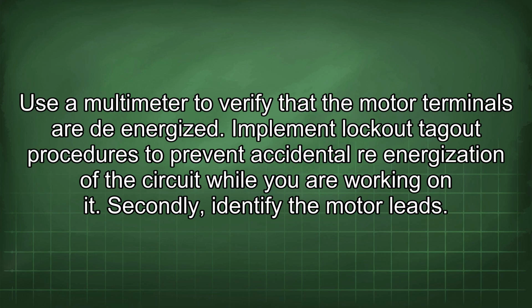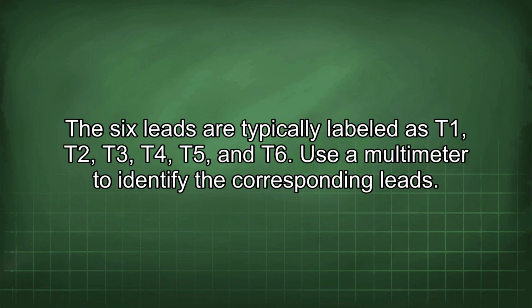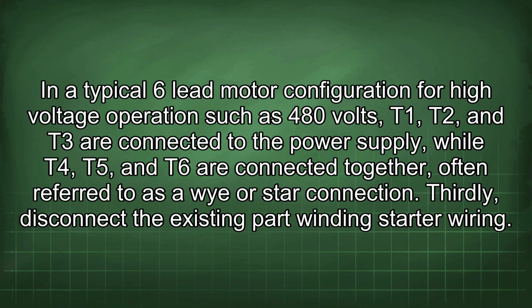Secondly, identify the motor leads. The 6 leads are typically labeled as T1, T2, T3, T4, T5, and T6. Use a multimeter to identify the corresponding leads. In a typical 6-lead motor configuration for high-voltage operations such as 480 volts, T1, T2 and T3 are connected to the power supply, while T4, T5, and T6 are connected together, often referred to as a wye-star connection.